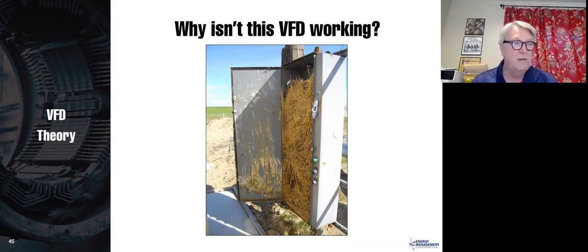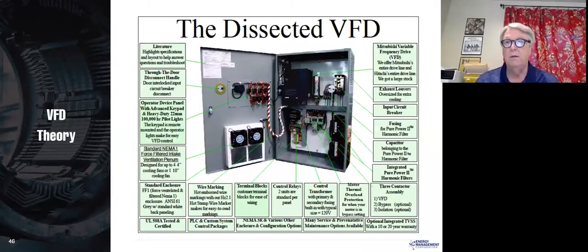If you want VFDs to last a long time, your religion should be keep them clean, keep them cool, and keep them dry. Those are the three rules of VFD longevity: keep them clean, keep them cool, and keep them dry. And having filters on a steel enclosure that protect your drive certainly keep that thing very clean, and also tend to keep it cool and dry. So, little advice that is not rocket science, but something to think about.